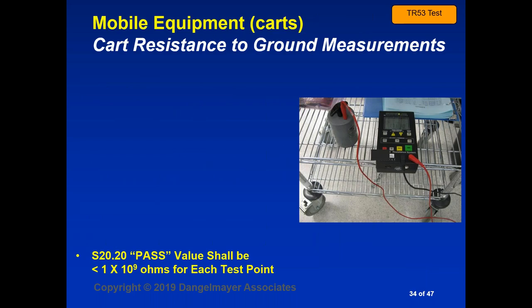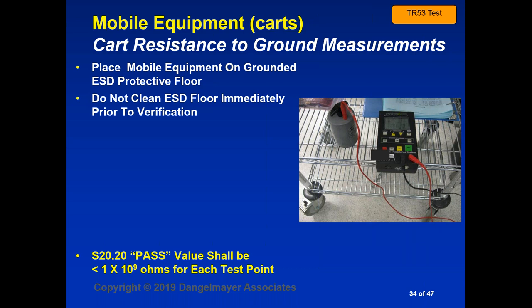I have a picture here. You see your mobile cart. You see your one electrode on the shelf of the cart, and your meter that's connected to AC ground. So place the mobile equipment on your grounded ESD protective floor, because that's what is going to be providing the grounding. Do not clean the ESD floor immediately prior to verification. You want a real test here, real life. You want to remove all the sensitive items from the mobile equipment just as a precaution, because your electrode is going to be putting voltage on the cart.